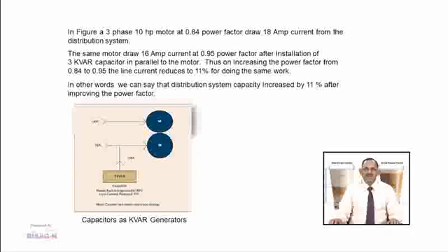In other words, the distribution system capacity increased by 11% after improving the power factor. The 3 kVAR capacitor connected in parallel to the motor supplies 3.6 amperes, while the motor draws 16 amperes from the line, compared to 18 amperes when the power factor was 0.84. In this case, the capacitor bank is working as a kVAR generator.